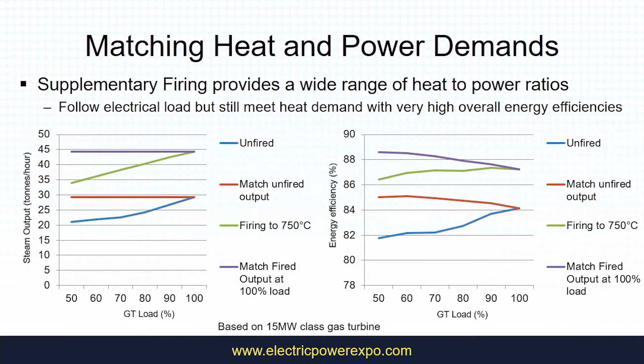That enables you to undersize your gas turbine. So you don't need a 15 megawatt unit to produce exactly the amount of steam if your factory load is only 7 or 8 megawatts. And that gives you a lot of decoupling of heat and power very reasonably easily. And the other thing about supplementary firing is because your exhaust gases are already at 500 degrees C or thereabouts, you're not heating air in your boilers from ambient conditions up to the 750. You're already starting from a high temperature point, so your efficiency with supplementary firing adds an extra 2, 3, 4, 5 percentage points efficiency on your overall energy efficiency of the plant.